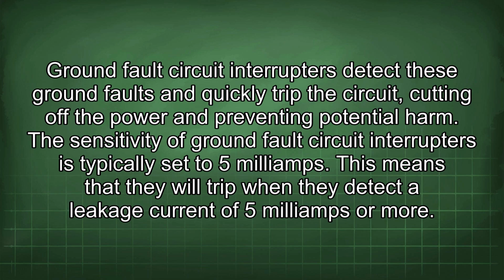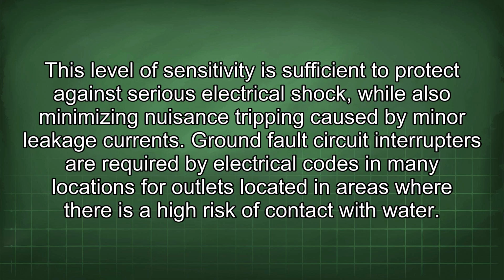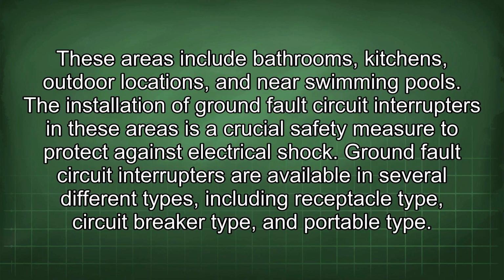This means that they will trip when they detect a leakage current of 5 mA or more. This level of sensitivity is sufficient to protect against serious electrical shock, while also minimizing nuisance tripping caused by minor leakage currents. Ground fault circuit interrupters are required by electrical codes in many locations for outlets located in areas where there is a high risk of contact with water. These areas include bathrooms, kitchens, outdoor locations, and near swimming pools. The installation of ground fault circuit interrupters in these areas is a crucial safety measure to protect against electrical shock.